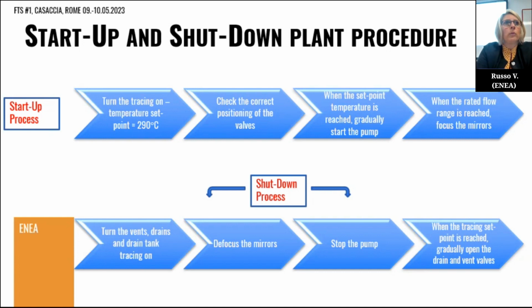And the plant starts operation in a normal condition. The same procedure can be done for the shutdown. At this time, we have to turn on the tracing on the vents, drain valve, and drain tank, in order to permit the salt to drain in this component. After, we have to defocus the mirrors and stop the pump, so the circulation of the salt.